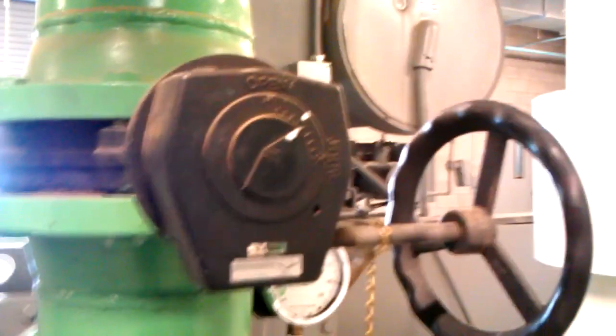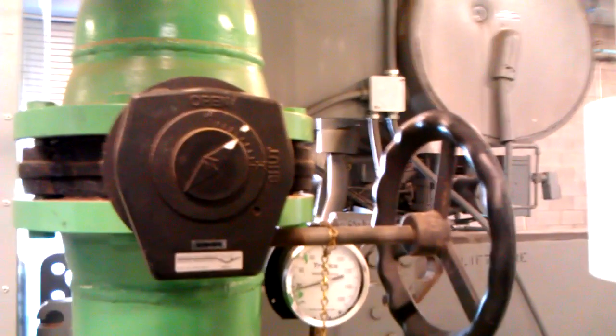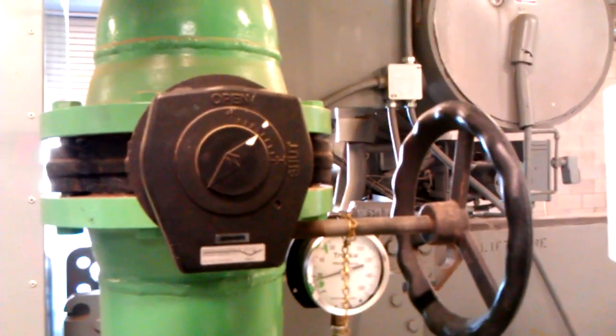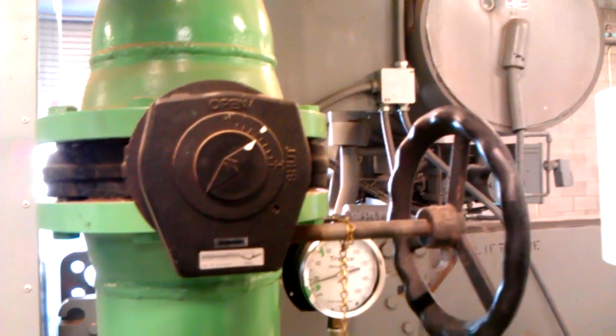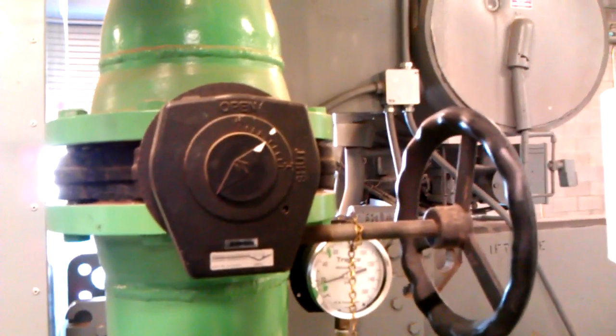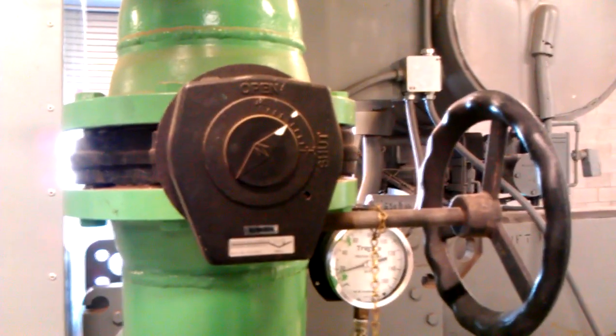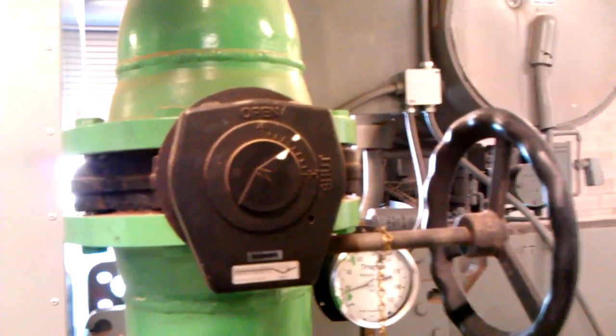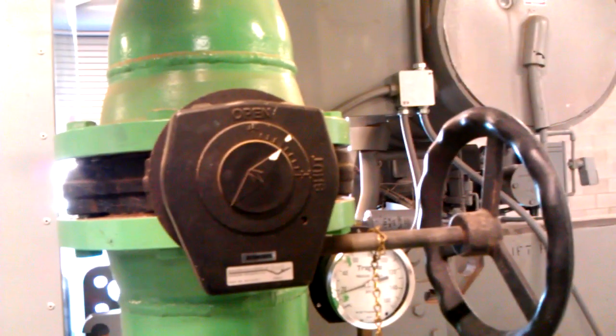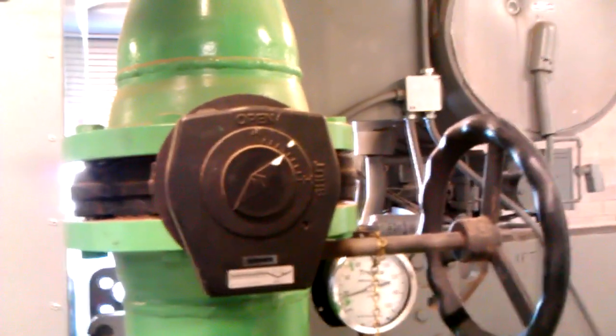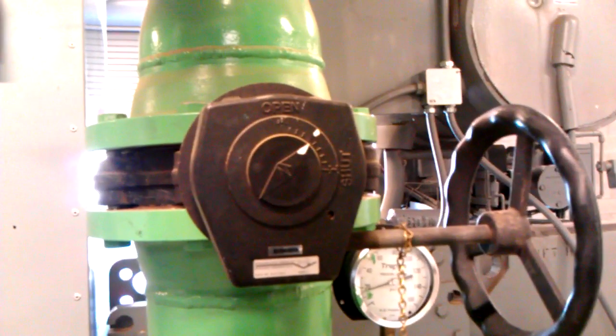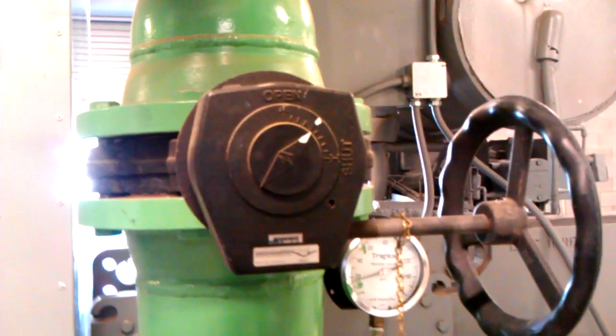Now I got all the valves put back where they belong. That way the system's ready to go. If something happens to chiller number 1 or a pump associated with it, the EMS or somebody can connect to the EMS and switch over to chiller 2. Start up all the appropriate pumps and start up the chiller. Of course, the one thing that prevents that is if those screens get a lot of silt on them. If you stop one pump and start up the other one, when the water moves, it'll usually plug up the other one, which means somebody's got to come in and open that up and clean them. So we're doing good now, though.